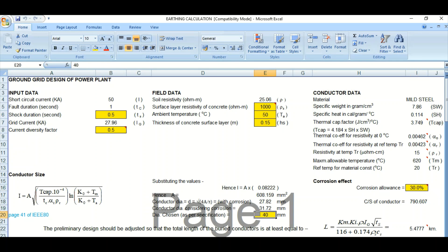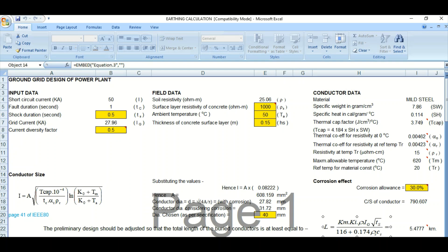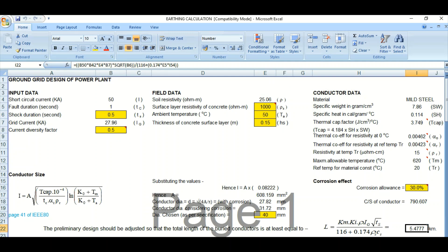Based on the calculation and the corrosion factor, a 40 mm diameter MS rod is selected for the preliminary design. The cross-section of this conductor works out to 790 square millimeters. This is the preliminary design, and it should be adjusted at site so that the total length of the buried conductor is at least equal to the minimum required length, as specified by IEEE 80.